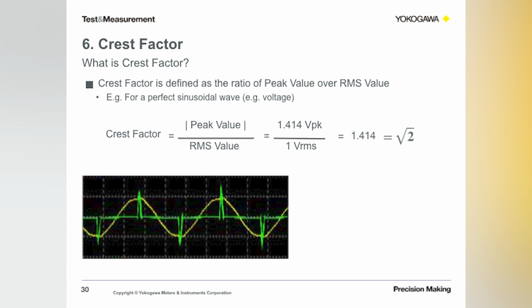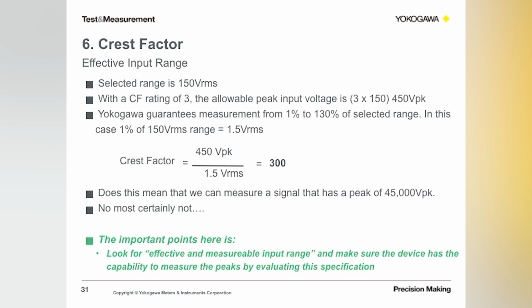So, should you be looking for measuring devices with a high crest factor rating, or should you be looking for a device that supports higher ranges so that you can measure these high peaks? We think it's more important to have a wider effective input range so that you can measure low signals and also have the capability to measure the high peaks. On Yokogawa power analyzers, the specified effective input range is 1% to 130% of the selected range. And the accuracy itself is actually guaranteed within that effective input range.